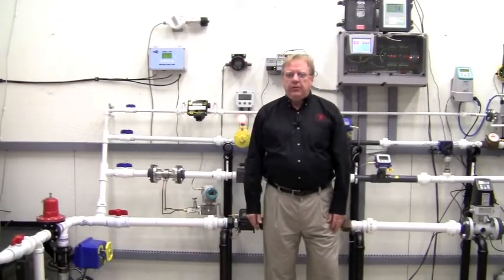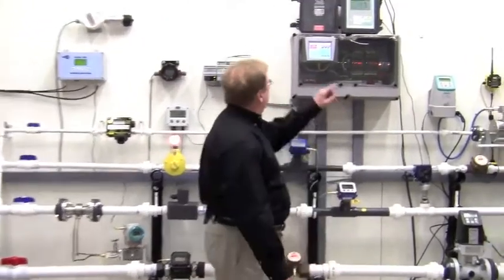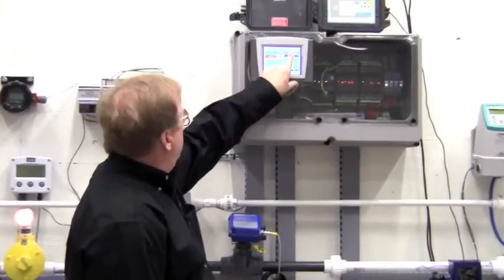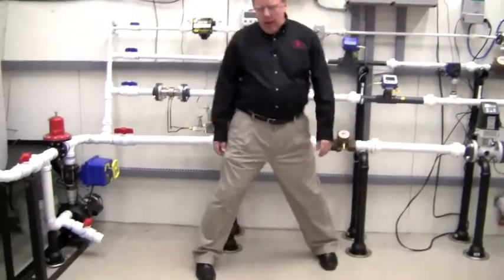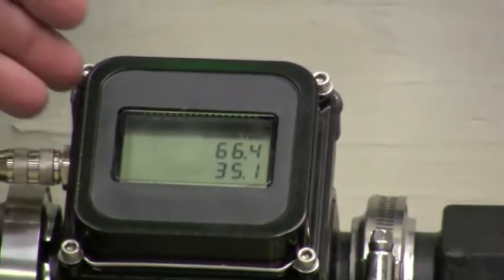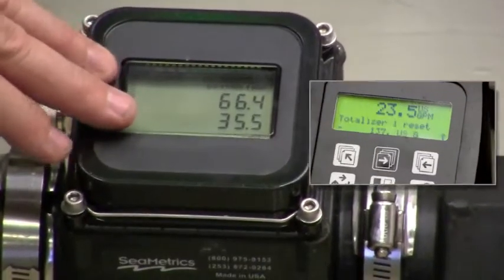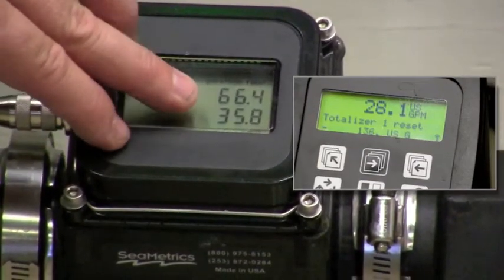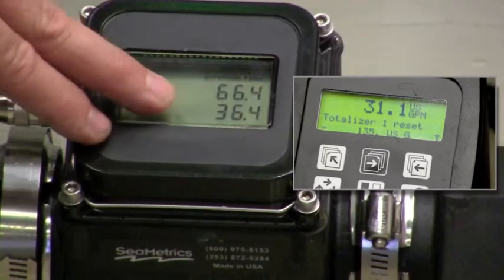Now let's do a comparison. I'm going to turn the pumps on and as you can see in our two-inch line our WMP, the flow is ramping up and it'll probably settle in around 36-37 gallons per minute.